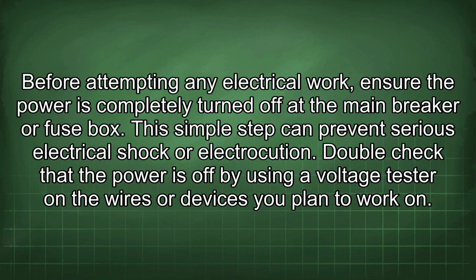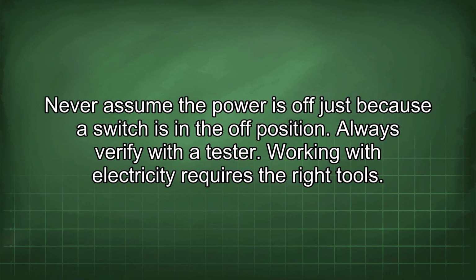Before attempting any electrical work, ensure the power is completely turned off at the main breaker or fuse box. This simple step can prevent serious electrical shock or electrocution. Double check that the power is off by using a voltage tester on the wires or devices you plan to work on. Never assume the power is off just because the switch is in the off position. Always verify with a tester.